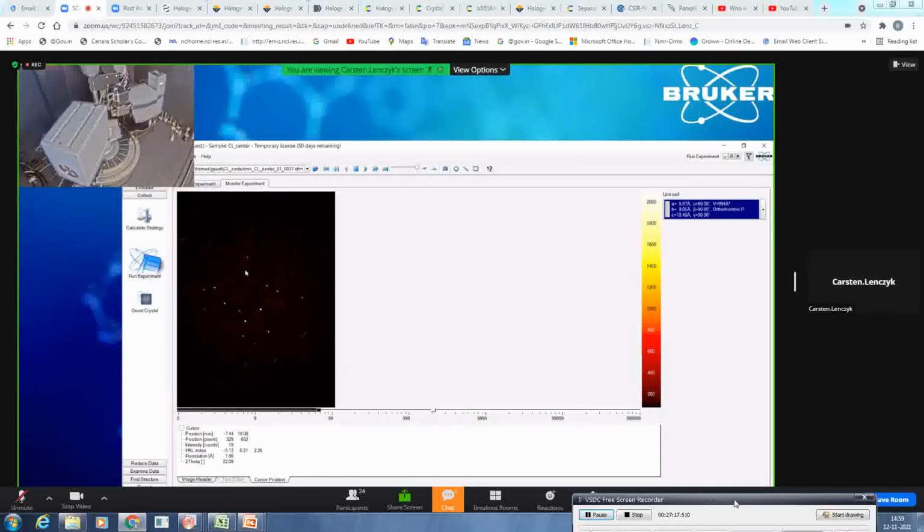C and M are for chemical or biological crystallography, specified for those 2 types, because in biological crystallography you most of the time use copper or softer radiation, while for chemical crystallography, most of the time molybdenum is used. And this has to be accounted for in the conversion material, because the harder your radiation, the more it can go through your conversion material. So you need a slightly thicker layer if you want to go for hard radiation like silver or indium.